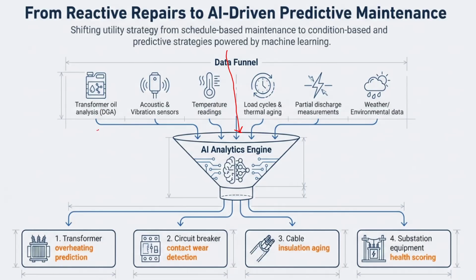Inside the transformer we have the oil level indication, so what we get is the level and also the temperature of that oil, and various other parameters like the acoustics and vibration sensors. Why is this very important? Because if the transformer is vibrating too much, there's a chance it may break. For that reason we have to collect the acoustics and vibration sensor details as well.